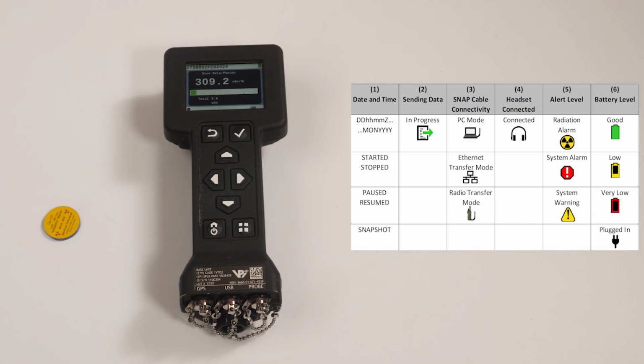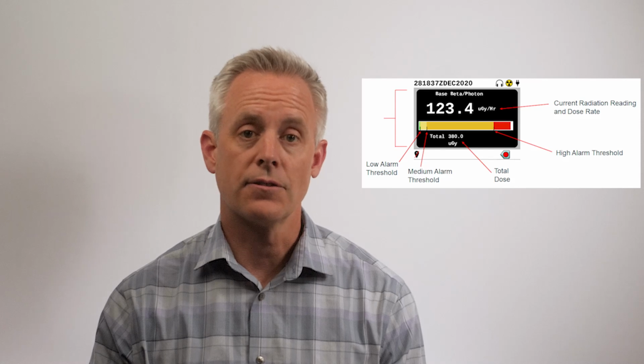battery power is bypassed. The middle of the home screen displays the radiation reading panel for the base unit detectors, which detect the presence of beta radiation and measures gamma radiation. If a probe is attached, the radiation reading panel will split and typically show the base unit readings on the left and the probe readings on the right. But what is displayed can be configured in the settings screen. Units of measurement are displayed after the radiation reading and can also be configured in the settings screen.